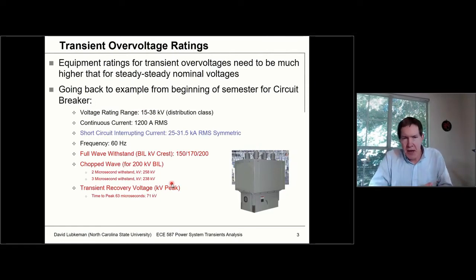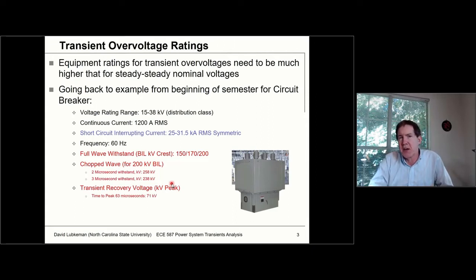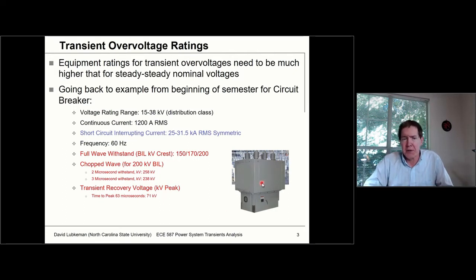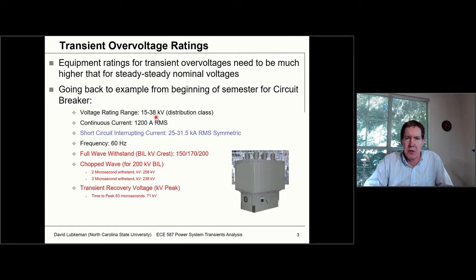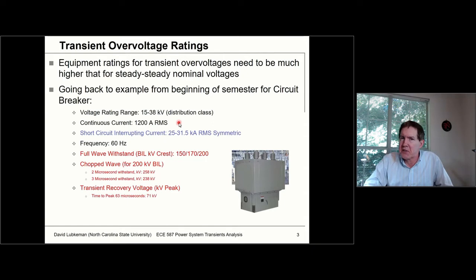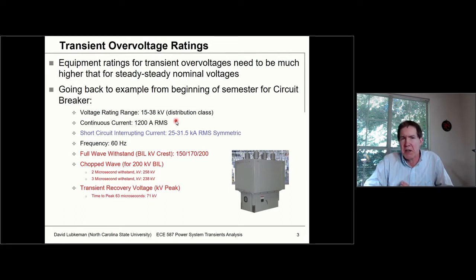Getting back to how we started the semester: transient overvoltage ratings are different than nominal ratings. For the circuit breaker we discussed, this was a distribution class circuit breaker with rating ranges between 15 and 38 kV, corresponding to nominal values of the distribution circuit. These are steady-state phasor-type values. The breaker has a continuous current rating — a phasor-type value — where this particular breaker could handle 1200 amperes of current continuously, which is more or less your load current.